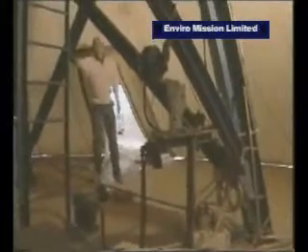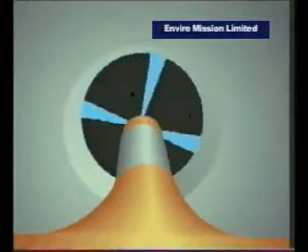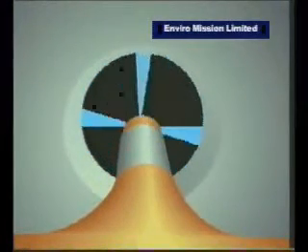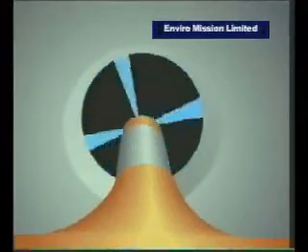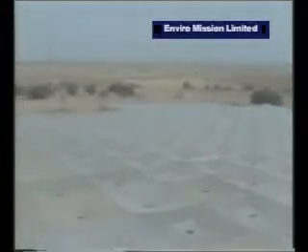In here is the turbine, supported quite independently of the rest of the chimney on a big steel tower, about 9 meters above. The four blades can be adjusted while the turbine is running to maintain a constant speed, or an optimum one of about 36 kilometers an hour. This pilot plant has generated a maximum of 60 kilowatts, but over a test period it averaged about 30 kilowatts of power output. Despite its size, the solar chimney was built in Spain for not much more than a million US dollars, which means that even the pilot plant is considered an economic proposition.